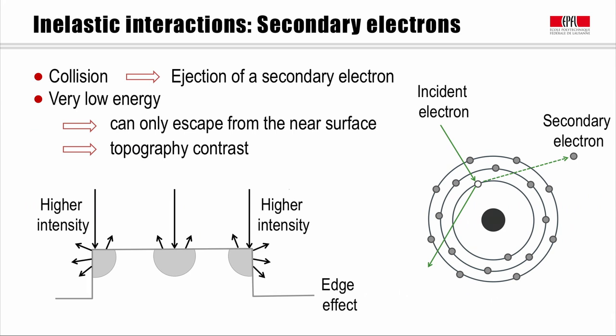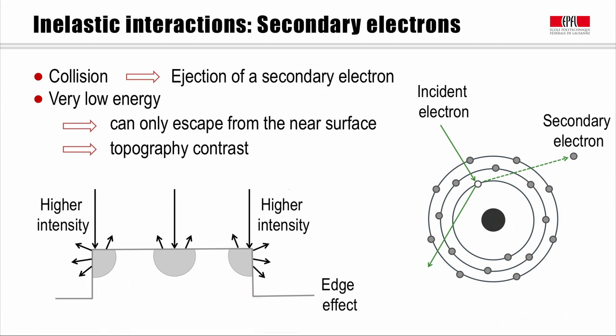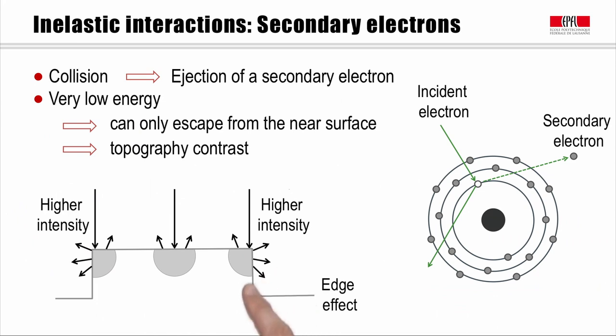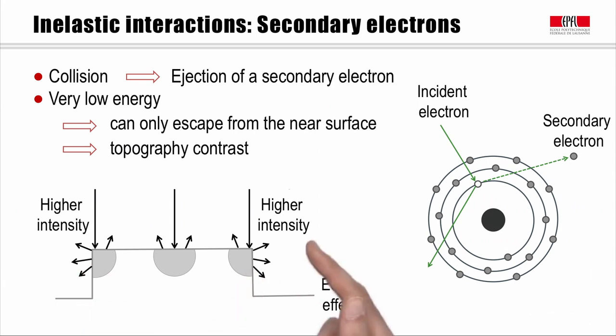The contrast obtained with secondary electrons is a topographic contrast. Three points are shown where incident electrons are sent, and you can see that this volume is where secondary electrons can escape and be detected. At the edges, more electrons can escape the surface and thus be collected. This means that on the image at these specific points, we get more signal and a brighter contrast.